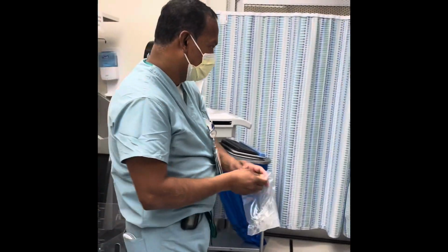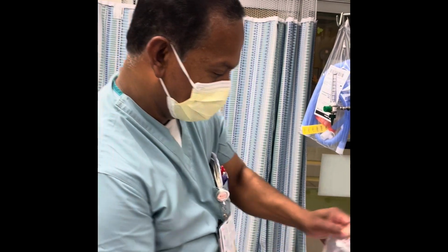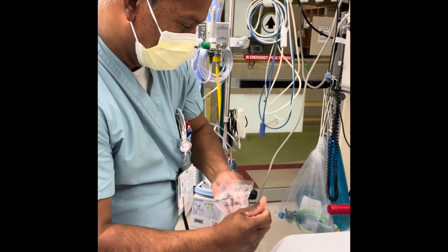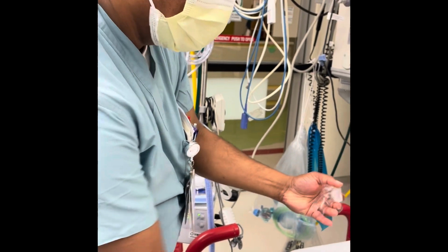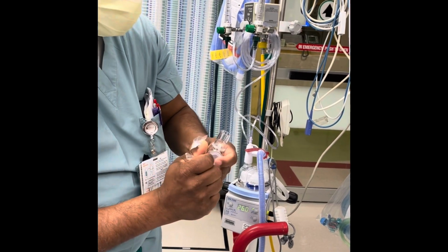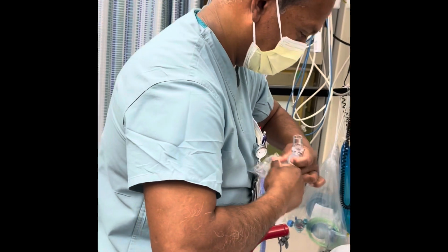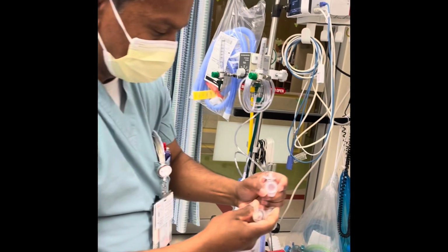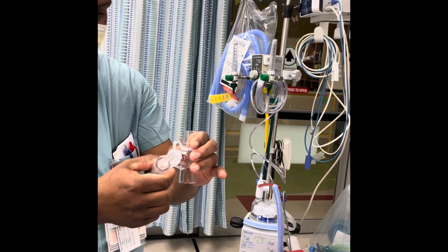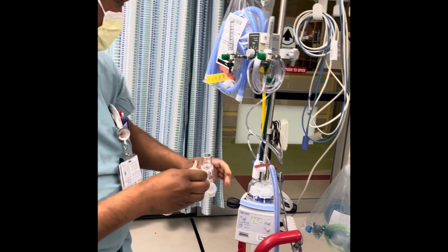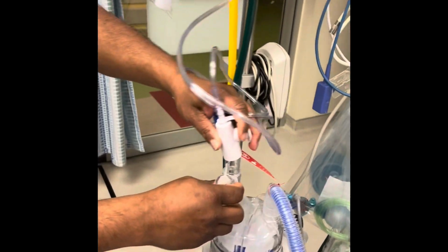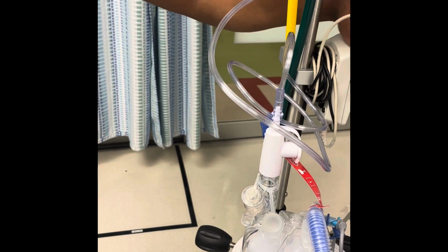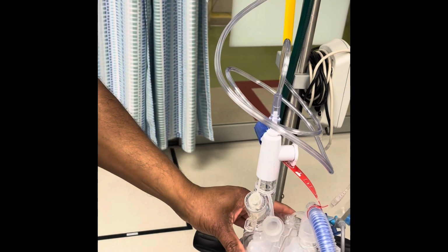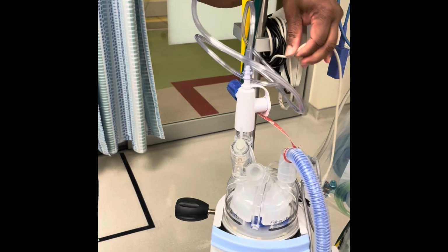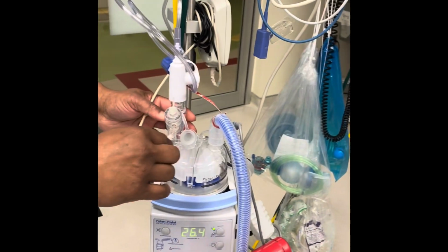Then if we have to give a neb treatment, we can do that through the Aerogen system. We have the nebulizer. This is a special piece that has to be hooked up if they're getting nebs. We also have it in our storage area, so it is available. It comes in one kit, and all we have to do is attach these two here and place it on the dry side of the chamber, so much more medication is delivered to the patient when it goes through the humidified air. The particle size will be lower when we nebulize it through the chamber too. That's the reason why we put it on the dry side.